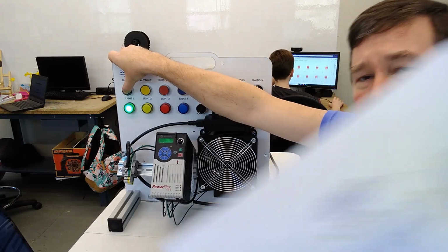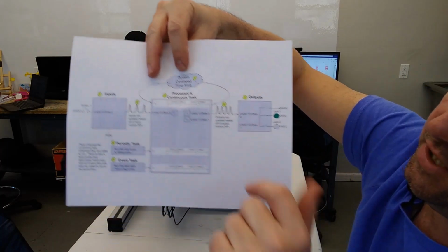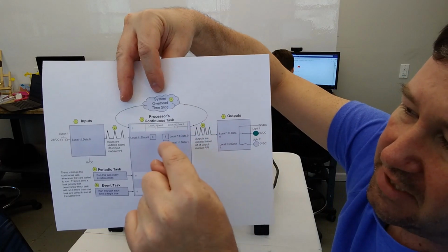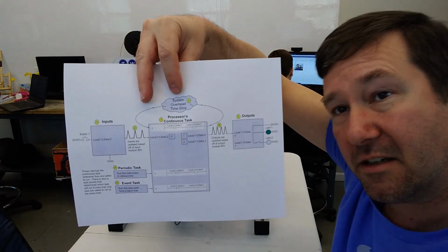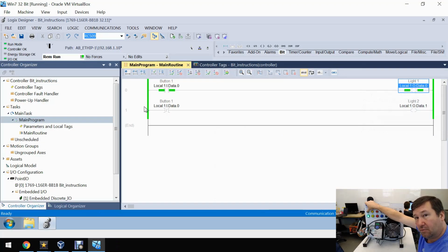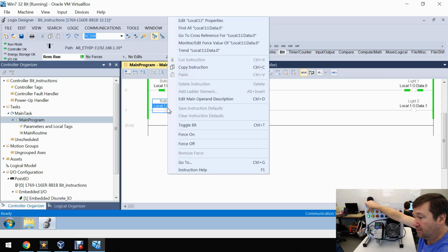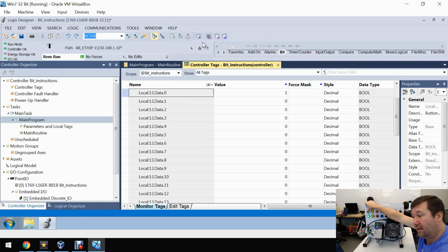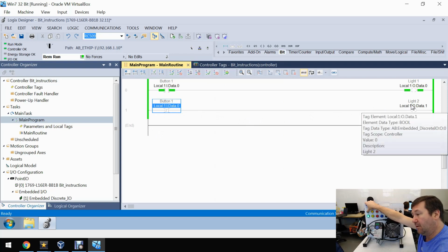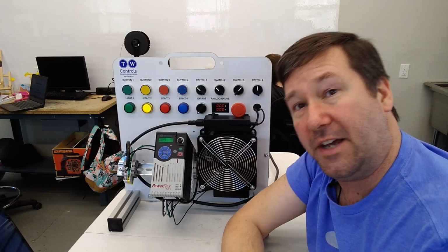And then, while we haven't been through the scan cycle too much yet, at a set interval, actually it's called the RPI, the PLC is going to take whatever's in these boxes that we're seeing in the controller tags and it's going to update. So after the OTE, it's going to go over to rung one. This is going to say, go look for a zero. Where at? Input 1. Do I have one? No, I have a one and it's looking for a zero. So it's going to pass false conditions on to this OTE and a false OTE is going to write a zero. Where to? Output 1.